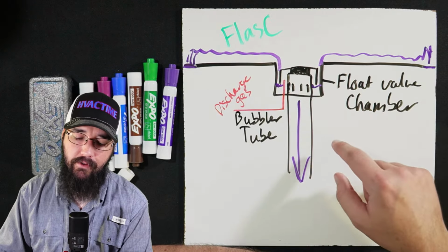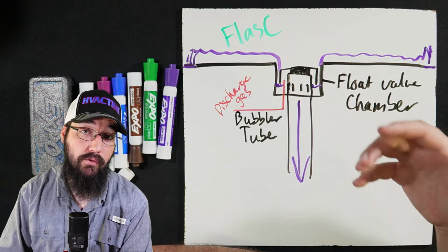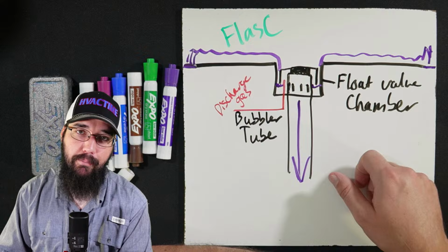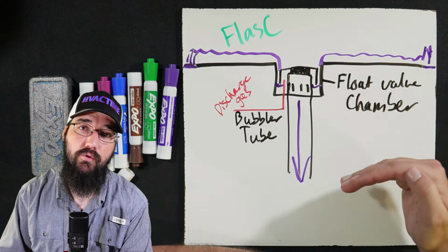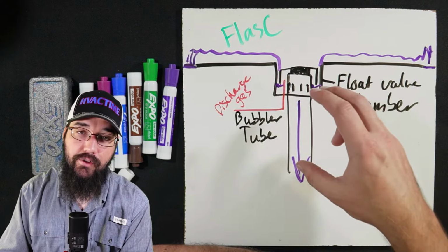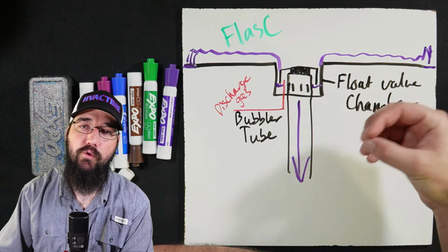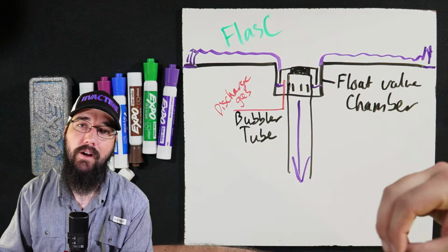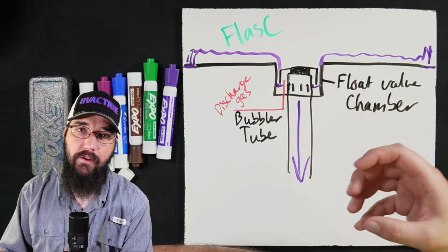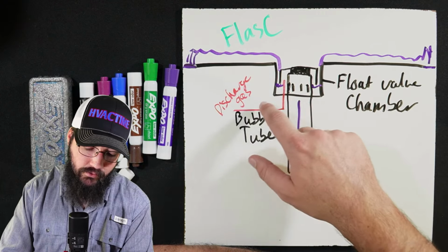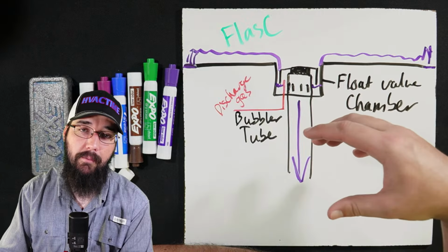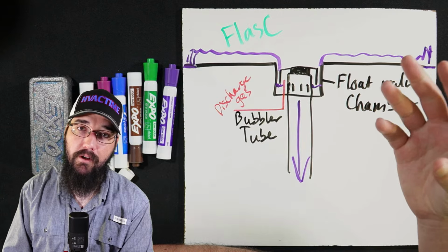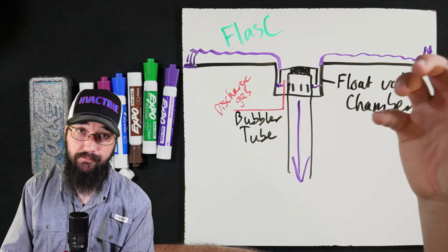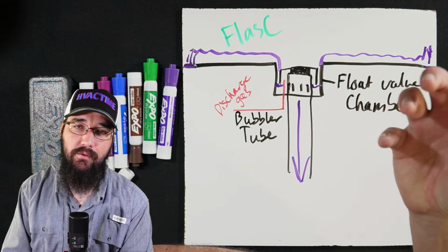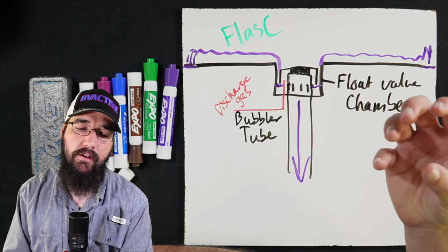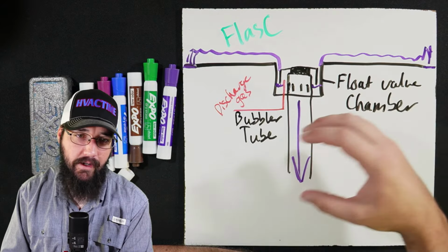This is where having a correct refrigerant charge in these machines is very critical, because it's going to have a heavy impact on this metering valve's ability to control flow through it. It's engineered so that it's responding to how much liquid there is, which responds to how much load we're pushing through the chiller and how much it's had to load up. So that's what this bubbler tube is doing this entire time: letting this constant little stream of bubbles enter this bowl assembly so that it has buoyancy and is able to float up and down on the liquid refrigerant level. That is its entire goal and purpose.